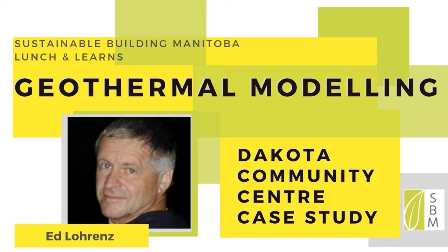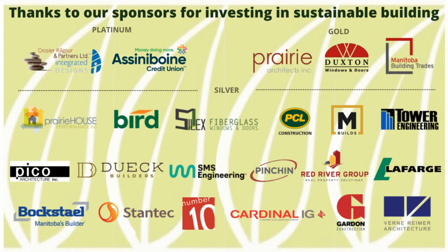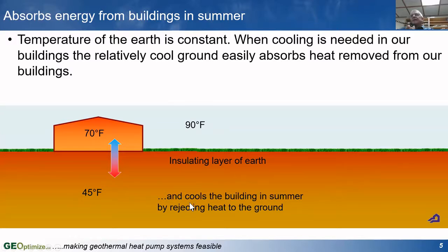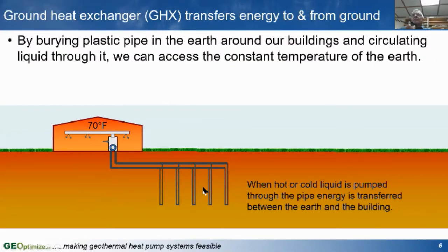People and animals have used the ground for many years, taking advantage of the energy stored in the ground. The ground is warmer than the air outside in the winter, cooler than the outside air in the summertime. What we need to do is bury plastic pipe in the ground to build a heat exchanger, circulate fluid through it, and run it through a heat pump. The heat pump either cools the water and warms the air that's going to the building, or cools the air and rejects the heat to the ground.